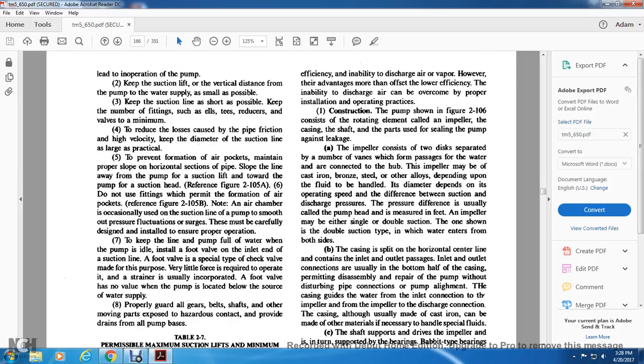Construction: the pump is shown in Figure 2.106. It consists of the rotating element called the impeller, the casing, the shaft, and the parts for sealing the pump against leakage. The impeller consists of two discs separated by vanes, which form the passages for the water, and is connected with the hub. The impeller may be cast iron, bronze, steel, or other alloys depending upon the fluid to be handled. The diameter depends on the operating speed.